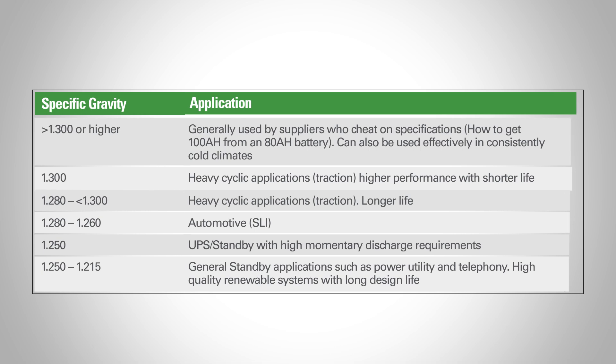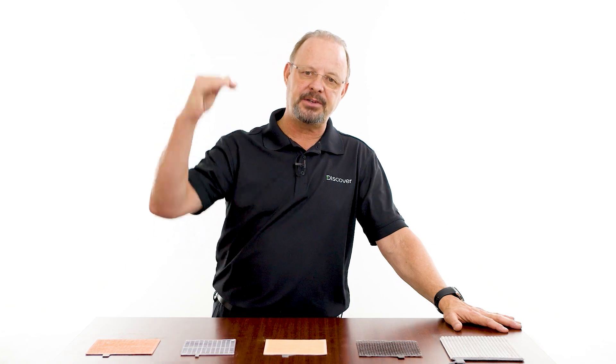Specific gravities higher than 1300 are generally used by suppliers who want to cheat on specifications. As mentioned earlier, you need the acid to be able to continue the discharge to get the total amount of capacity out of the active material in that battery.